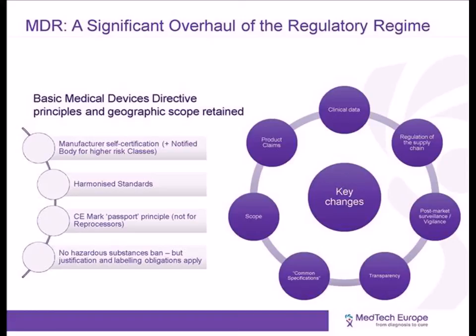The MDR also has a broadened product scope, meaning that it catches new, previously unregulated kinds of products. Going forward, non-medical or aesthetic products will be regulated under the MDR as non-medical purpose devices. For instance, cosmetic contact lenses, cosmetic fillers, and non-medical implants are all good examples of this. Devices offered to users in the EU via the internet are also in scope, as are devices used to supply therapeutic and diagnostic services via the internet on a commercial basis to people within Europe.